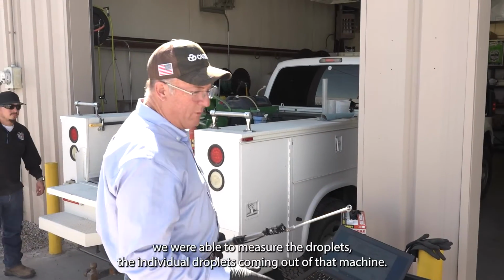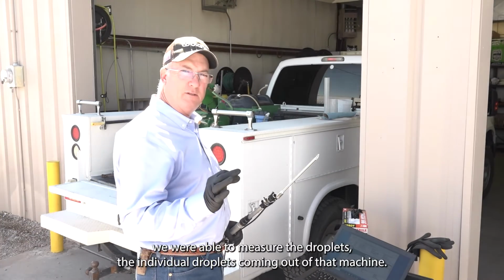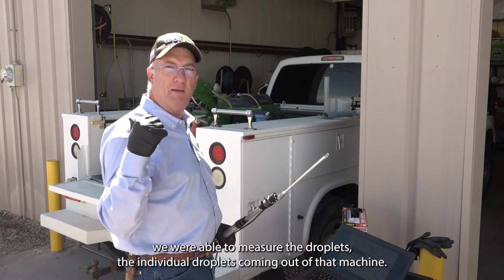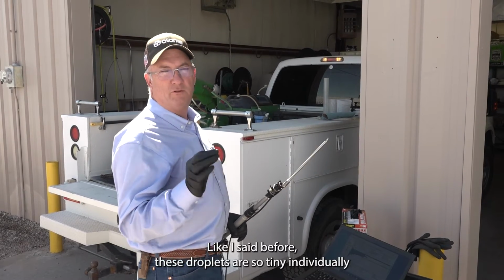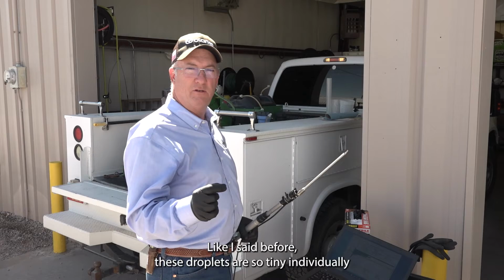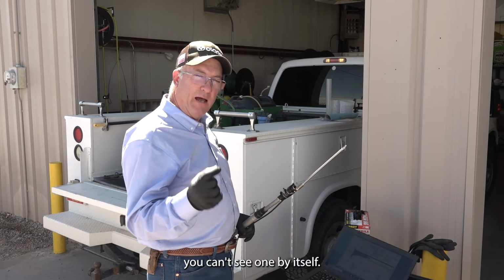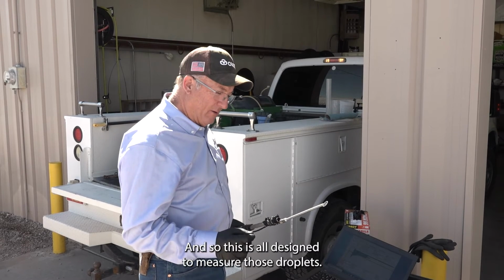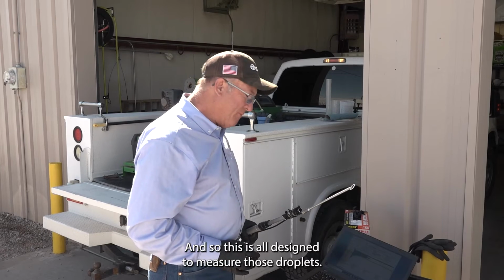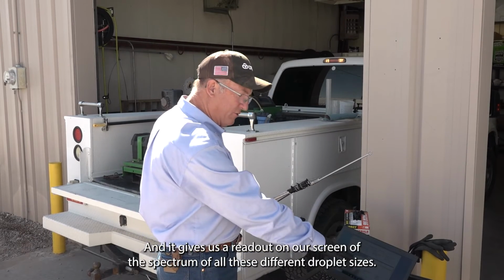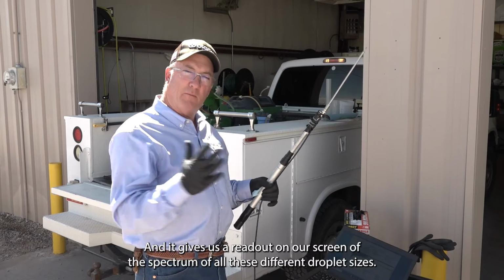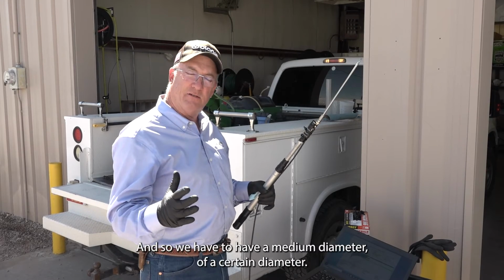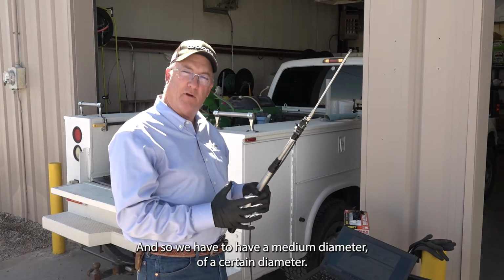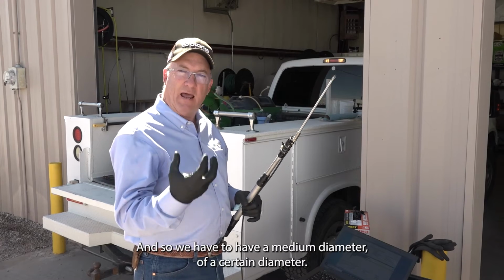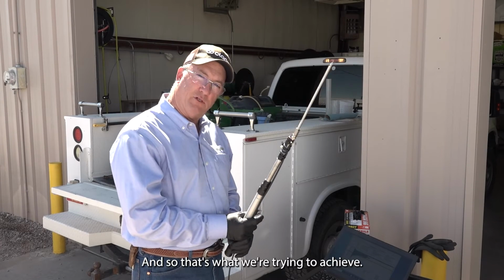Using this equipment, we were able to measure the droplets, the individual droplets coming out of that machine. Like I said before, these droplets are so tiny individually, you can't see one by itself. And so this was all designed to measure those droplets, and it gives us a readout on our screen of the spectrum of all these different droplet sizes. And so we have to have a median diameter of a certain diameter. And so that's what we're trying to achieve.